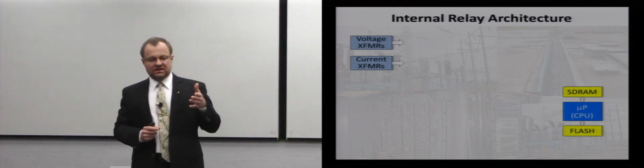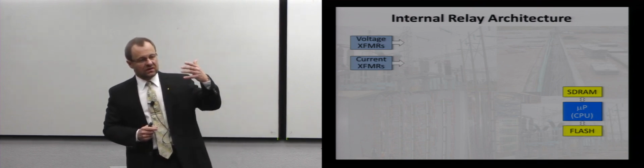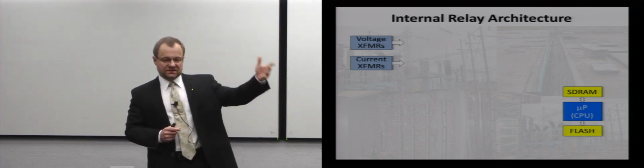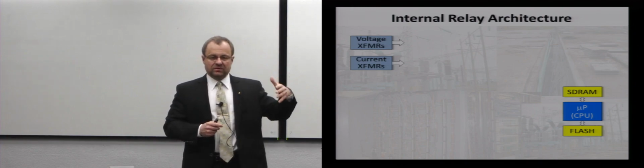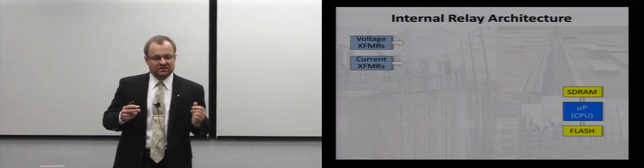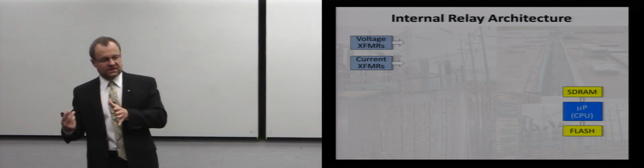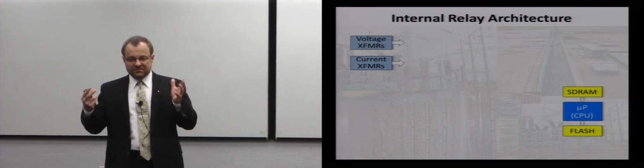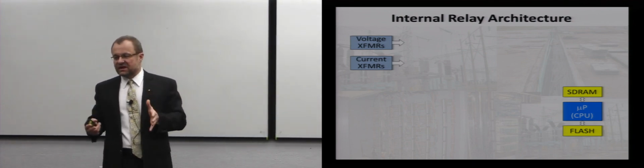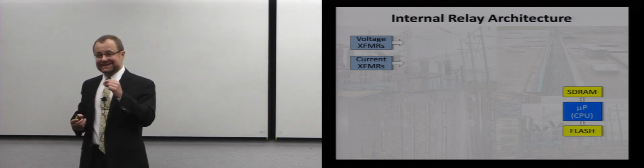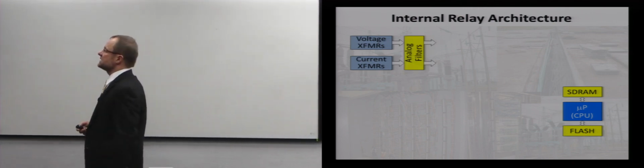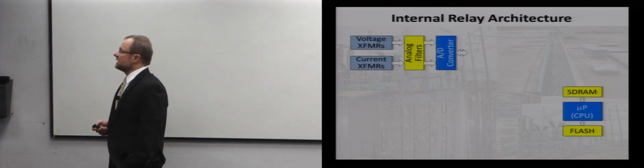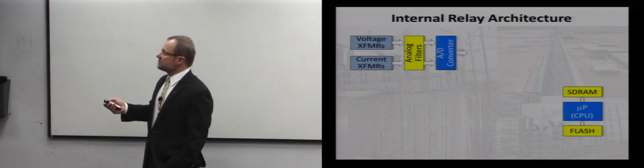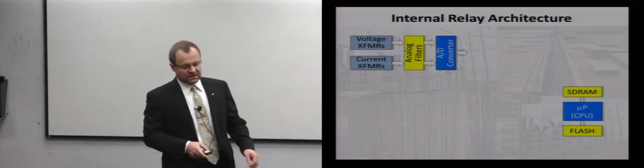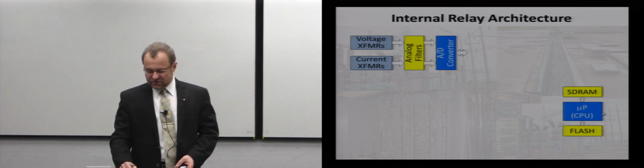You have to have galvanic isolation between the wires that go all the way to CTs and PTs and couple all the stuff that is in a substation and the clean part on the inside of the chassis when you have relatively fragile electronics that must be isolated from it. So those transformers are inside the relay for galvanic isolation. You have analog filters and you have your A to D converter. This is where your primary data is coming from, right? So this is where our primary information is. This is where we are going to process it.